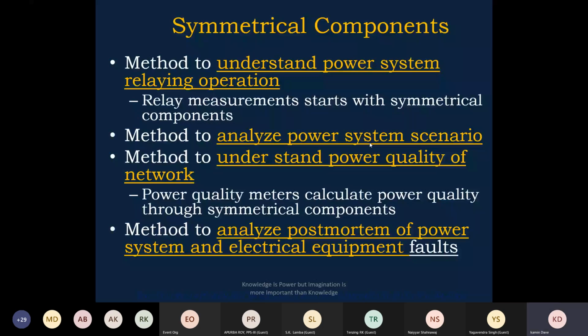Relay measurement starts with symmetrical components. As we discussed, relays are phasor based, and phasor-based relays calculate the symmetrical components, and then most of the critical logic involves sequence component interlocks. So measurement itself starts with the symmetrical components during a fault condition.